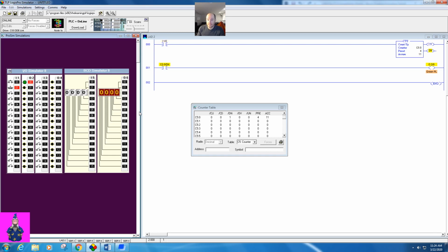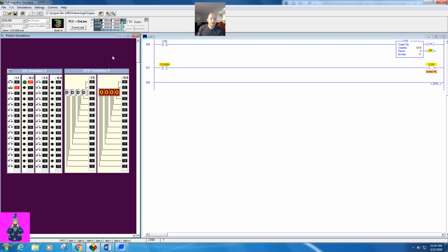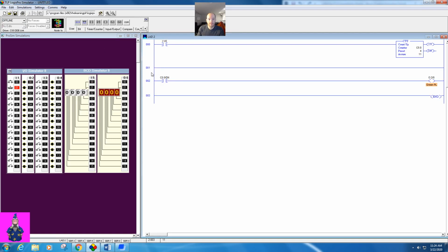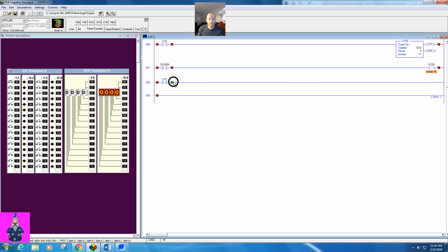Now, I didn't put a reset in here, so let me show you how we do that. We're going to go to program. Click here. Go offline. I'm not sure if that step is necessary, but we're going to do it anyway. Grab this line, drag it down to here. I'm going to drag this input down to here and double click on it and make this I:1/1. I'm going to come over here, right click to make this a normally open push button. Then I'm going to go back to my counter and grab my reset.